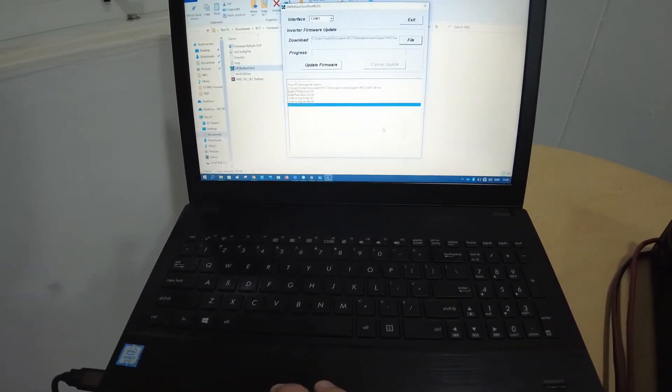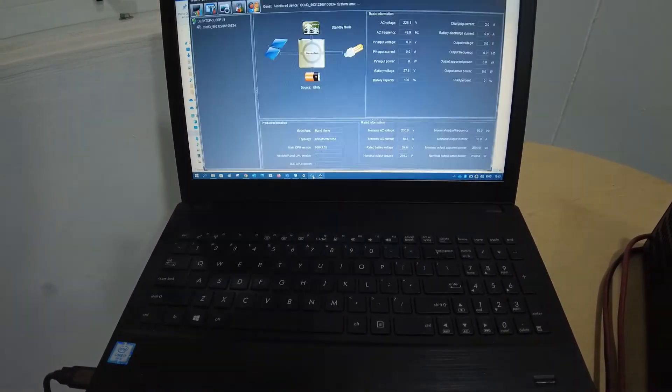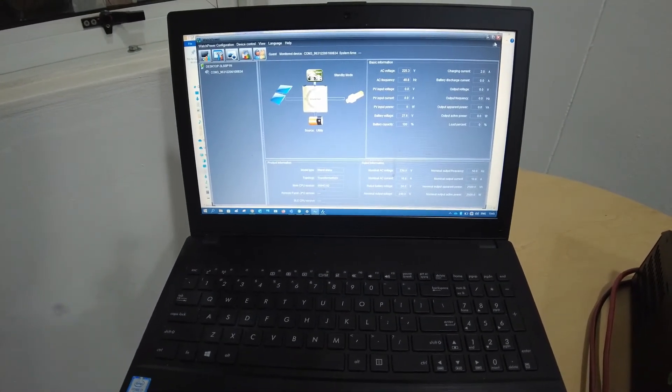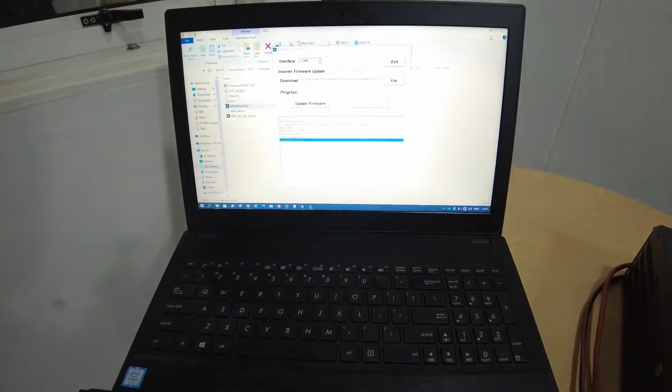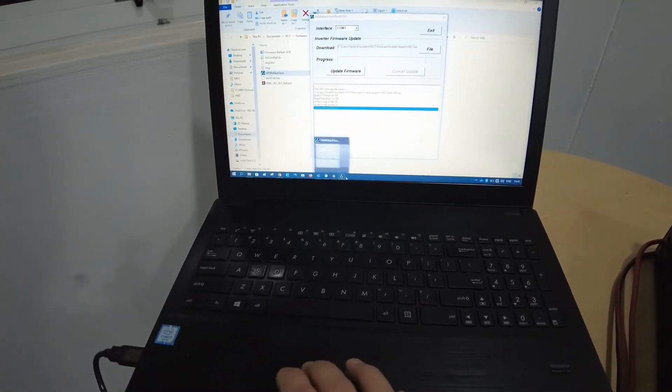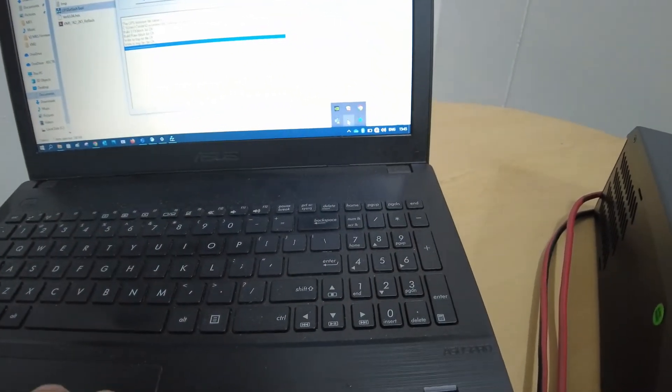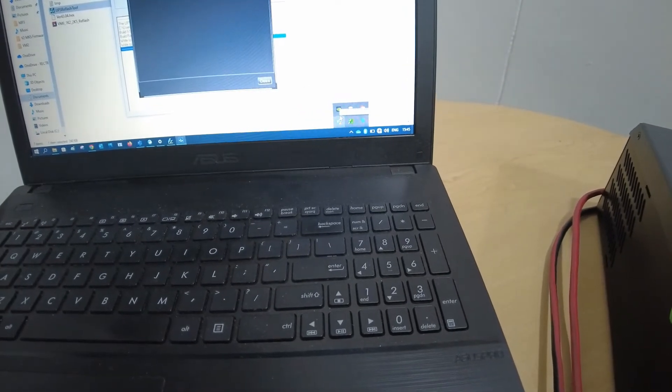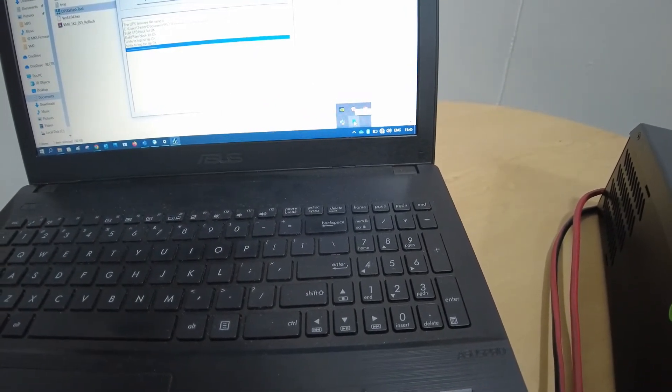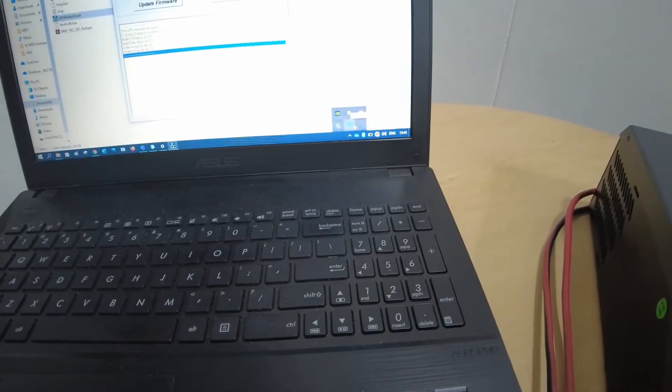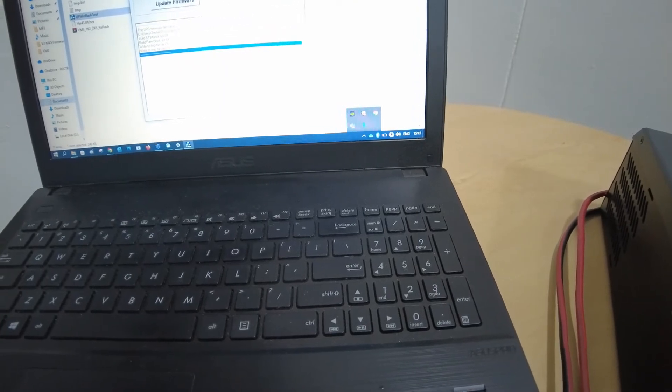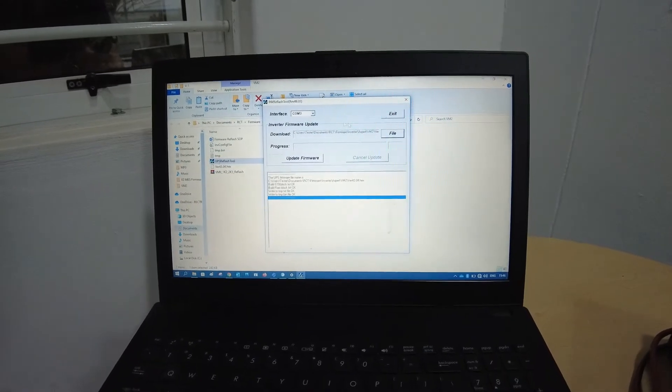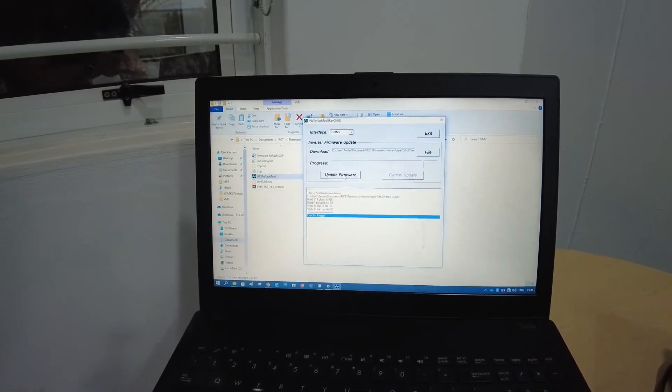Before we start, make sure if you're using watch power program to monitor the inverter that it is closed. So closing the file, you do not see it in the task bar at the bottom. However, it is still running in the background. Make sure you right click there, click on exit and make sure it is not running in the background. That will occupy your USB port and cause interference and will fail with the firmware update. So while that is on, we've selected the COM, we've selected the file. We can update firmware.